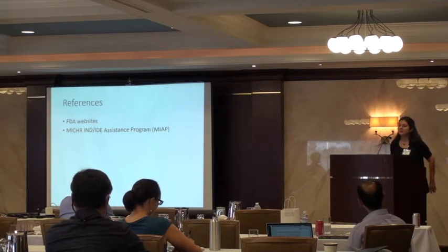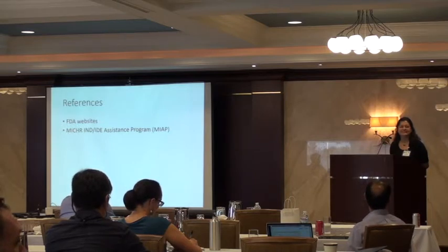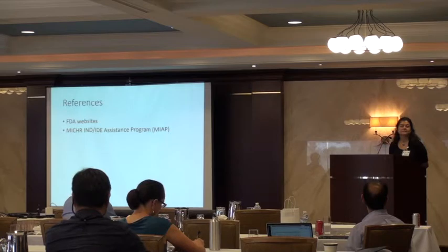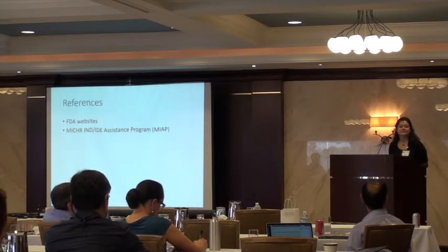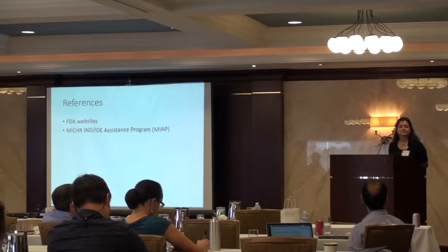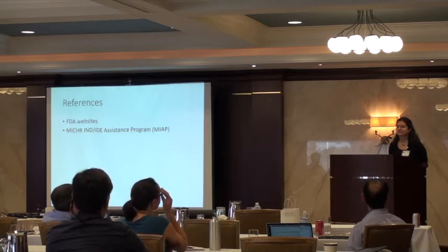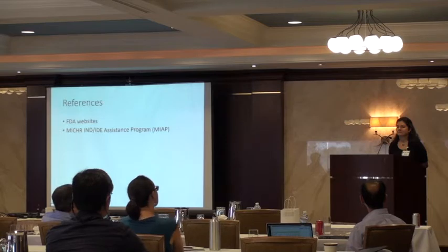I mean, it could be so obvious that, but there's a very low threshold for sending a proposal to the FDA and saying, we have a question for you before submission. Our question for you is, since we're using an already approved device in its intended manner, does this really need an IDE? And they'll say, no, we think you're using the device as it was intended to be used for years. Yeah. And I think you were next, yeah.